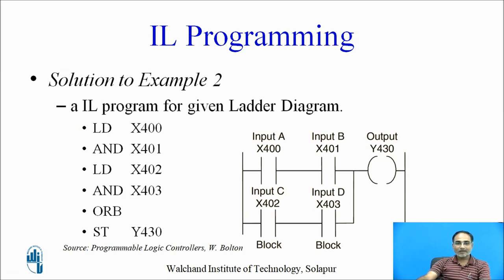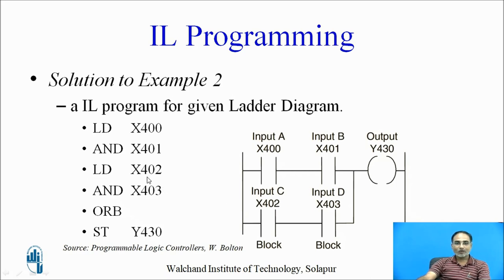Here is the equivalent Instruction List program. First, LD X400 reads the status of Input A, then AND X401 ANDs it with Input B. For the second block, LD X402 reads the status of Input C, then AND X403 ANDs it with Input D. These two blocks are combined using an OR instruction, and finally ST Y430 stores the result to the output.